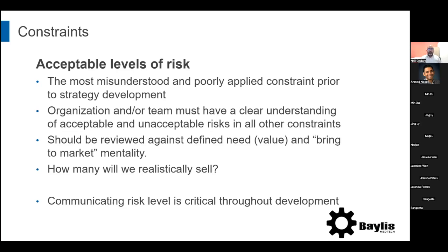Yeah, there's the risk there, just to kind of read between the lines, that you could go, like there are, for example, for the products we make, there are standards that govern how the device shall perform. We have our on-the-books V&V testing. This is the clinical test. This is the bench test. Everything passes. And if you were to limit it to that, depending on how comprehensive your formal testing regimen is, maybe you're okay.